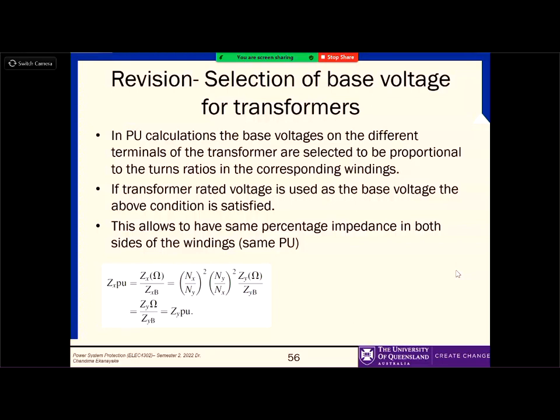But it's not always the rating of the winding if you are using a different tap setting. Have you heard about tap setting of a transformer? Let's say one transformer has primary 11 kV, and the secondary side can be changed from 129 kV to 132 kV, depending on the setting. So if you are using a different tap setting, you have to use the base voltage corresponding to that tap setting, not the nominal 11 kV to 132 kV. So if you are using 129 kV, your primary is 11 kV, the secondary base has to be 129, not 132, because I will explain why you need to use it.